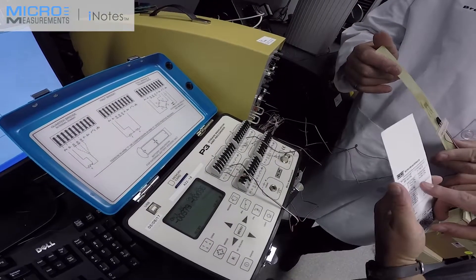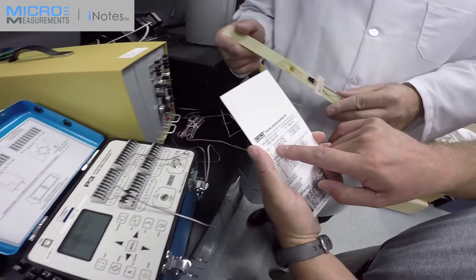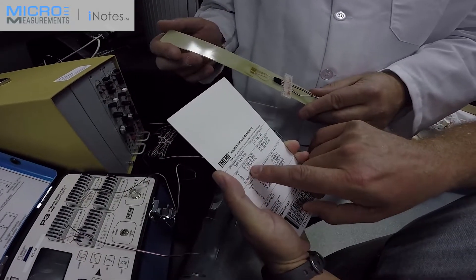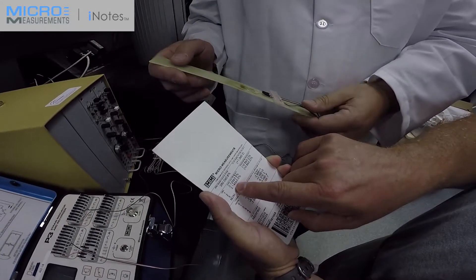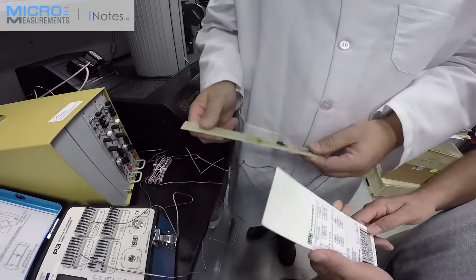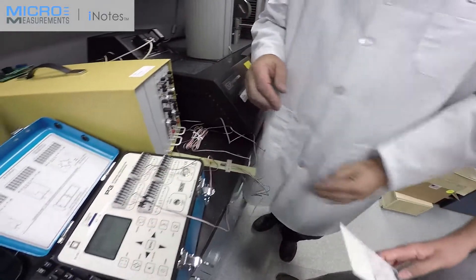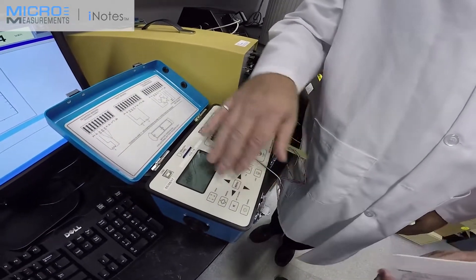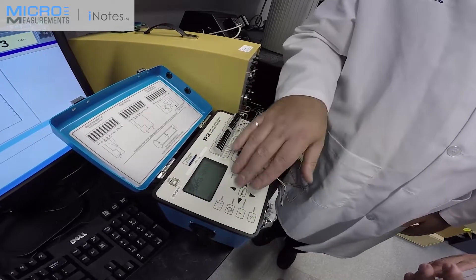And it looks like the gauge factor for grid one, the transverse is 2.12 and then for the axial grid is 2.14. So I'm guessing you can put that into the P3, correct? In the P3, basically, we have to define channels, bridges, type, and also the scaling. And then we can just start the recording.